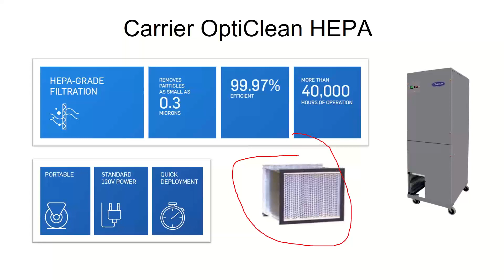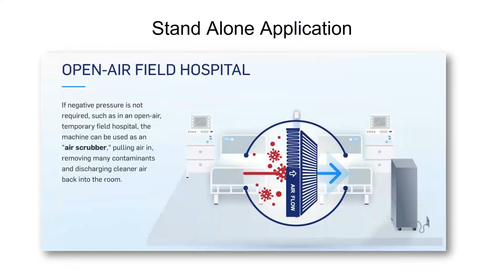If you've got a cooling system, you probably have a duct system, and you probably can do it a different way. You can use that equipment as negative pressure machines where they suck air out of the room, filter it, and discharge it outside. So like in an ICU area, that might be the case. Or you can just use it as a recirc machine to enhance whatever you already have going on in the space.